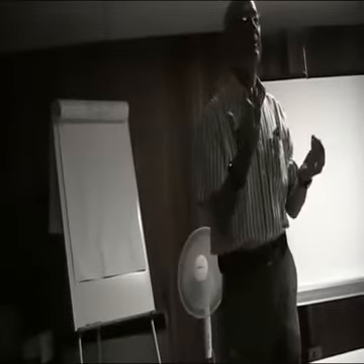But then again, the rule of thumb is if it's a fail open valve, you want that flow tending to open, because if the valve fails, you want the flow to assist the valve to open.